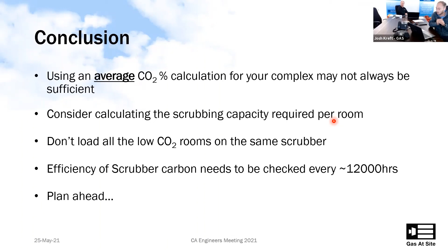And the efficiency of our scrubber carbon, we should check it roughly every 12,000 hours. That's quite easy to do. We just connect the analyzer like we saw in the previous example. So it's very important to plan ahead. It's important to know our rooms, what cultivars you're going to be storing, at what set points, and also to know our equipment and what their capabilities are and where they are in their life cycle.